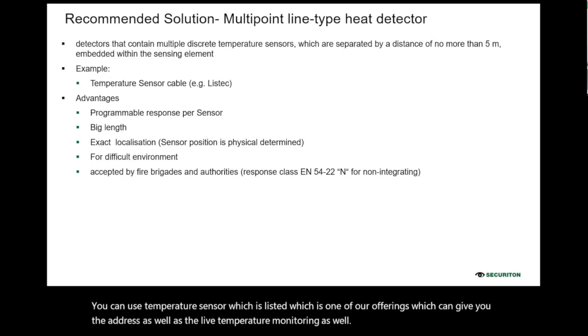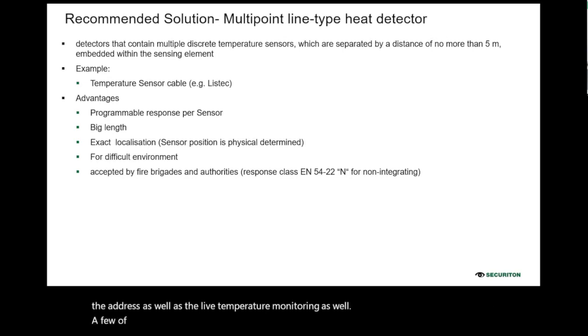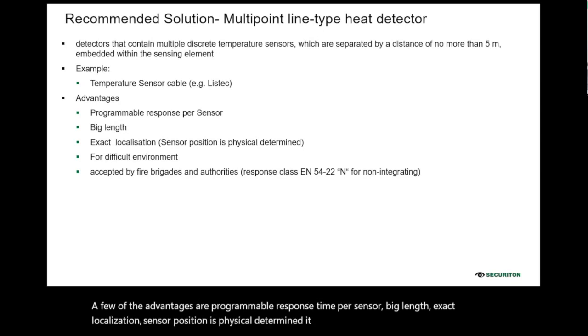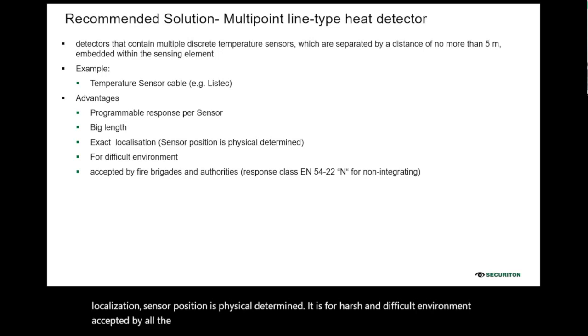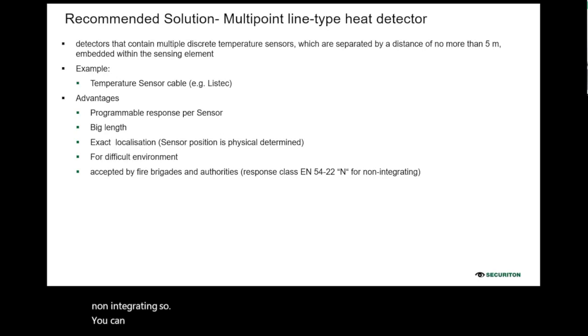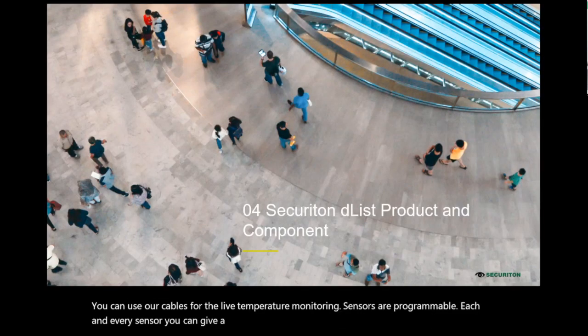A few of the example advantages are programmable response time per sensor, big length, exact localization, and sensor position is physically determined. It is for harsh and difficult environments, accepted by all the fire brigades and authorities. And the response class is EN54 part 22 and for non-integrating. So you can use our cables for live temperature monitoring. Sensors are programmable. Each and every sensor you can give different temperature settings.